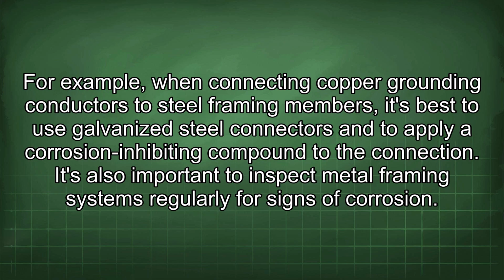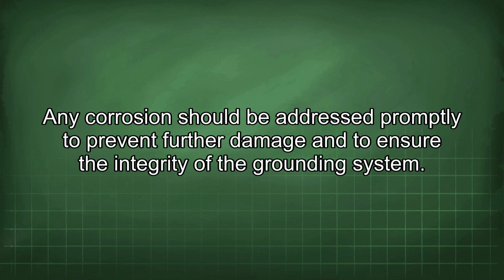For example, when connecting copper grounding conductors to steel framing members, it's best to use galvanized steel connectors and to apply a corrosion-inhibiting compound to the connection. It's also important to inspect metal framing systems regularly for signs of corrosion. Any corrosion should be addressed promptly to prevent further damage and to ensure the integrity of the grounding system.